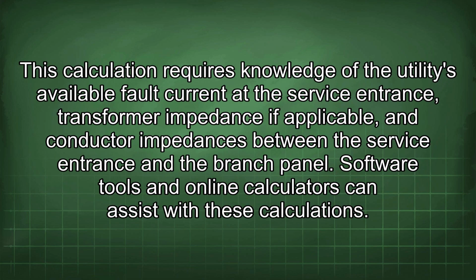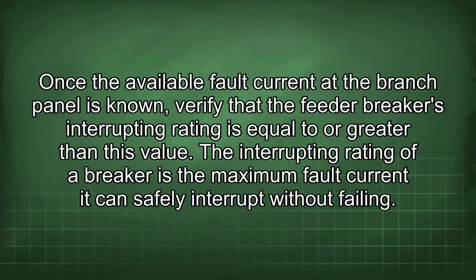To determine if series rating is appropriate, calculate the available fault current at the branch panel. This calculation requires knowledge of the utility's available fault current at the service entrance, transformer impedance if applicable, and conductor impedances between the service entrance and the branch panel. Software tools and online calculators can assist with these calculations. Once the available fault current at the branch panel is known, verify that the feeder breaker's interrupting rating is equal to or greater than this value.